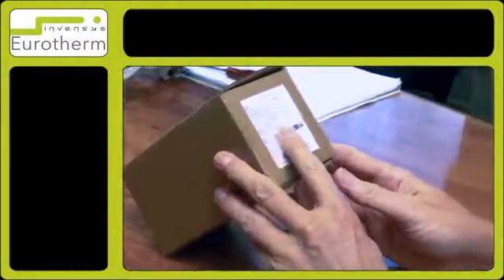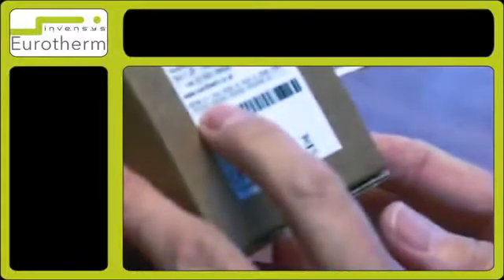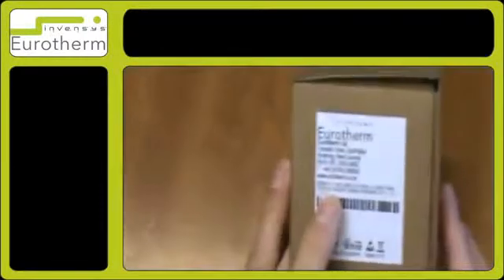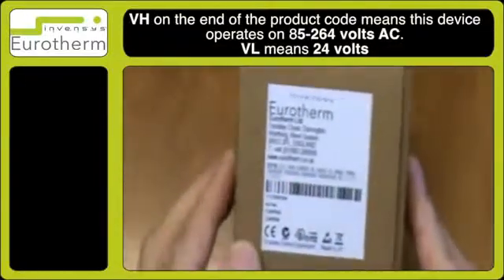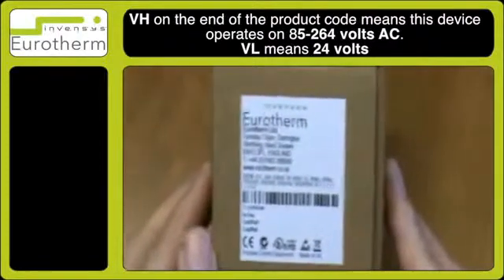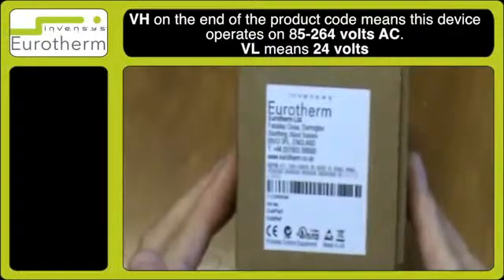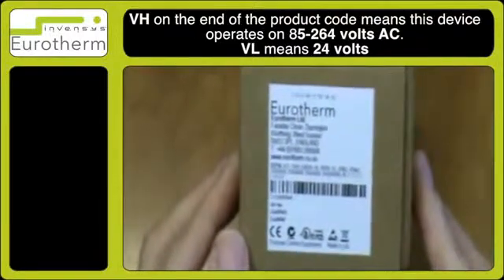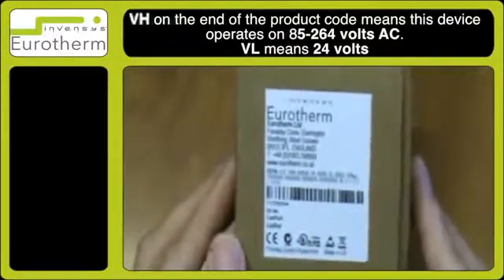Observe the label and you will see a product code. The product code will start something like 3216/CC/VH. Make note of VH - VH is important as it indicates the actual mains supply to the instrument. You can also have VL. VL is 24 volts, but VH is 85 to 264 volts AC.